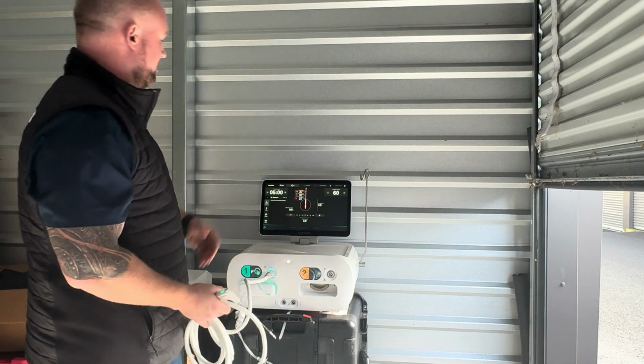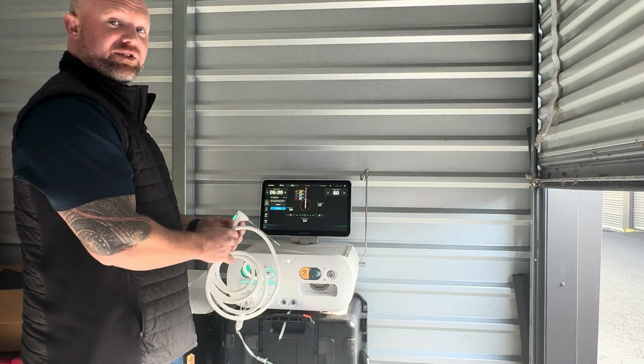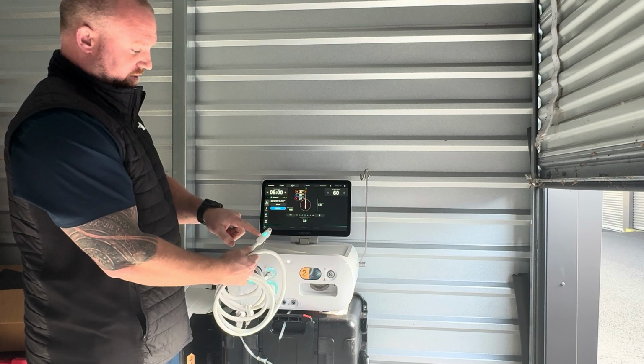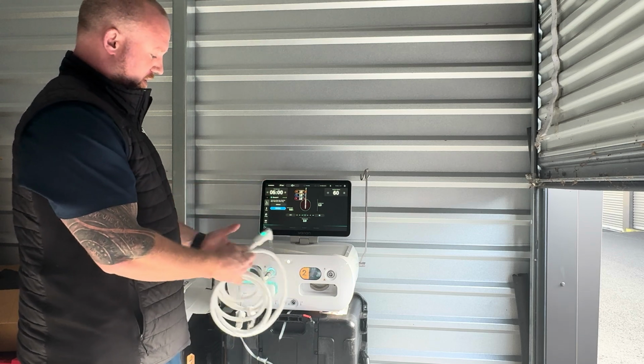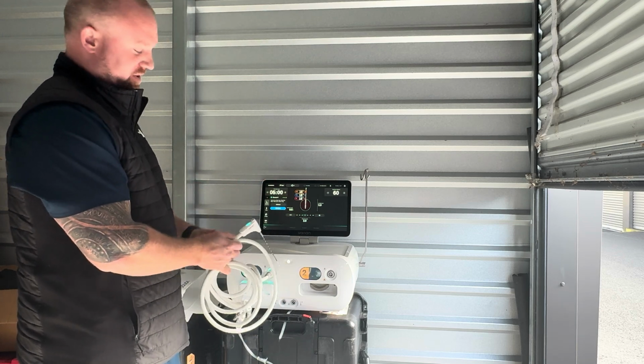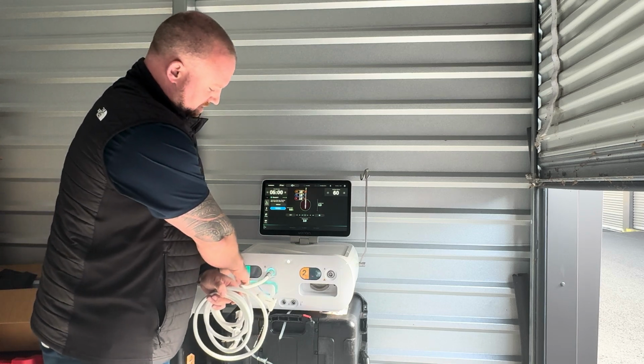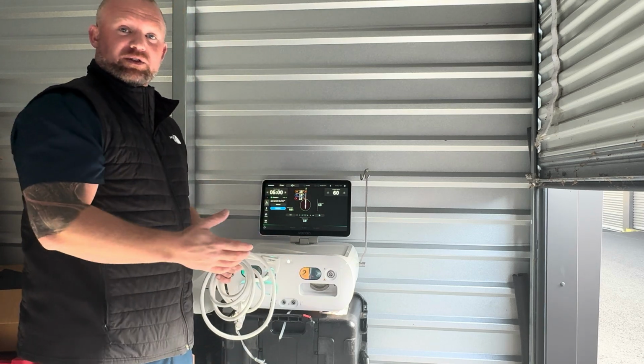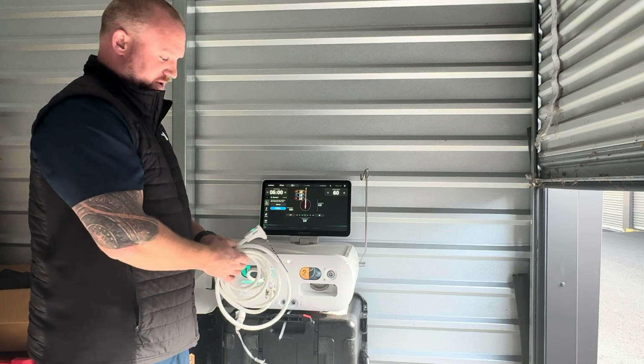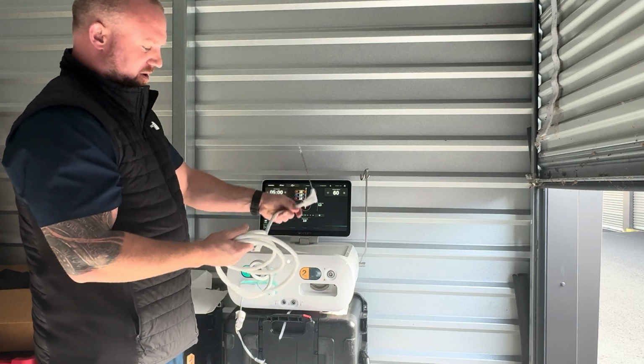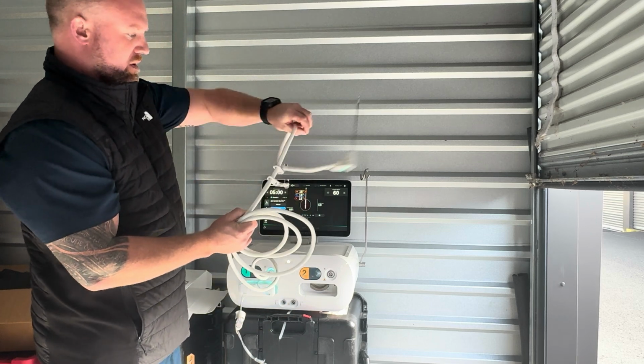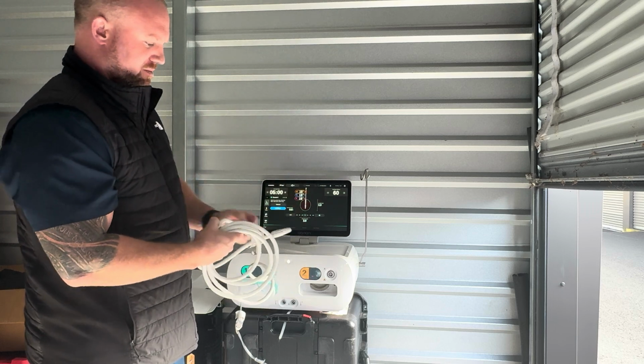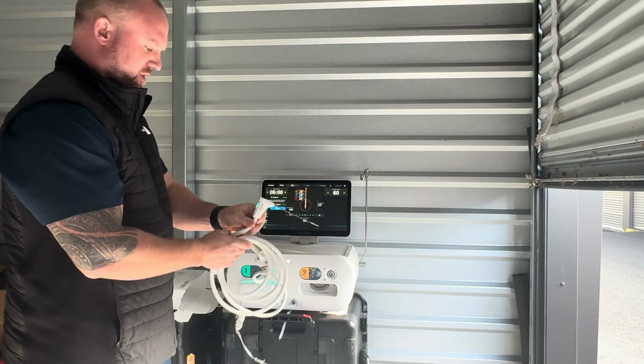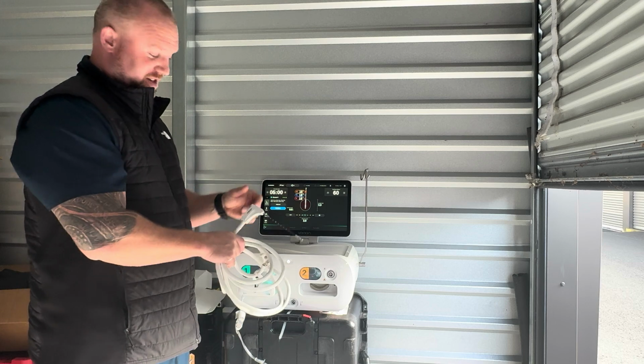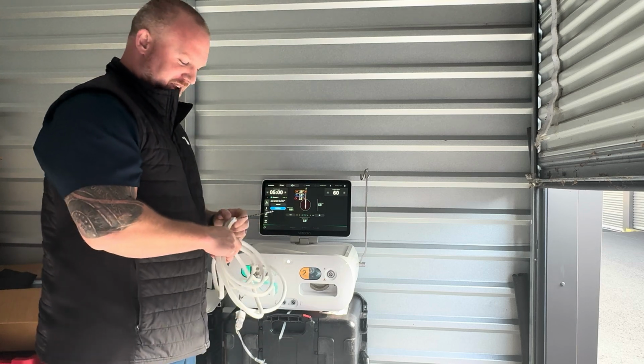And you'll hear these audible clicks letting us know that we are linked in. And you'll see these light up so that, yes, we know that we're actually linked up to the system. This one will always have this kind of teal color. This will be an orange color so that we never get the probes mixed up during the procedure. This probe itself has a couple clips on it, which allows us to hook to the bed, so no probes are falling off like you just saw a second ago. Luckily, this isn't going into a patient.